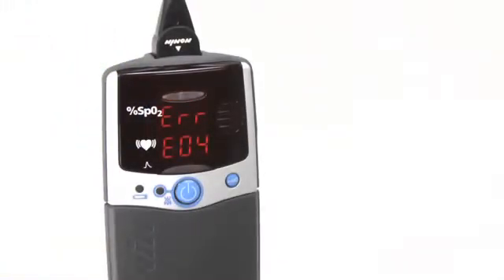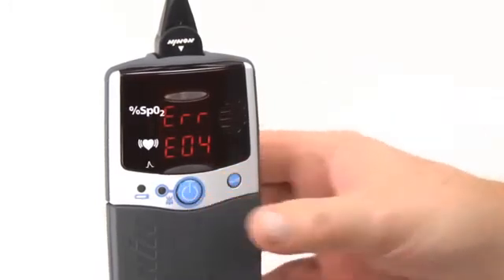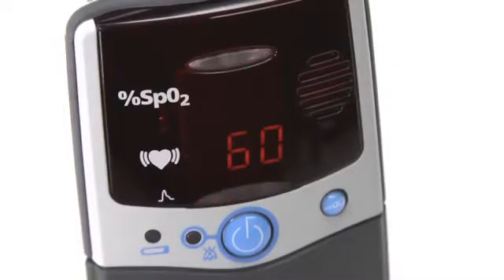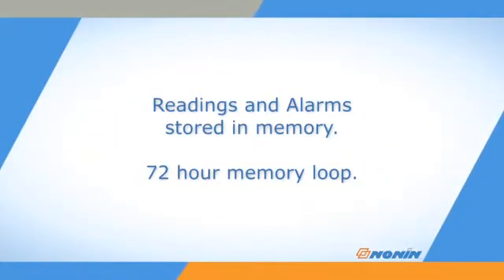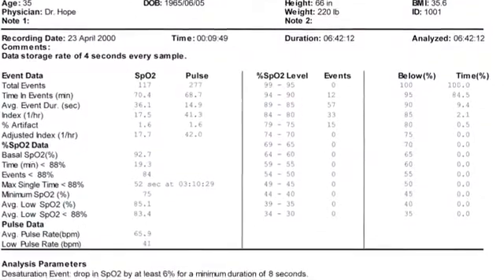Other alarms may occur on the oximeter. You can silence the audible alarm with the on-off button, then immediately notify your clinician or technical support contact. The oximeter will record the time and date of any alarm in its stored data, along with regular oxygen saturation and pulse readings. The stored data is retained for the last 72 hours of use and then records over the older data. Data can be downloaded and analyzed on Nonin Envision software.